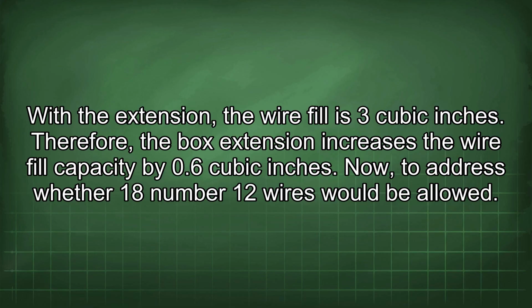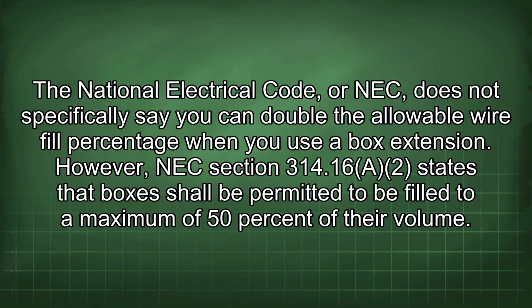Now, to address whether 18 number 12 wires would be allowed. The National Electrical Code, or NEC, does not specifically say you can double the allowable wire fill percentage when you use a box extension. However, NEC Section 314.16(A)(2) states that boxes shall be permitted to be filled to a maximum of 50% of their volume.